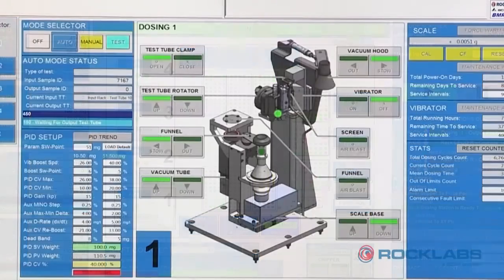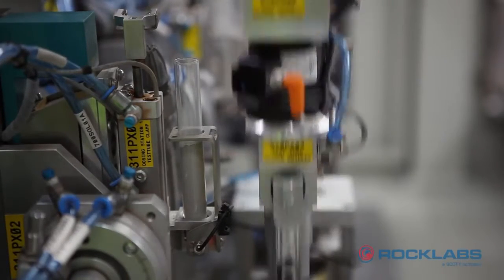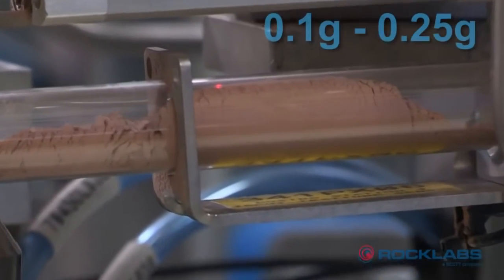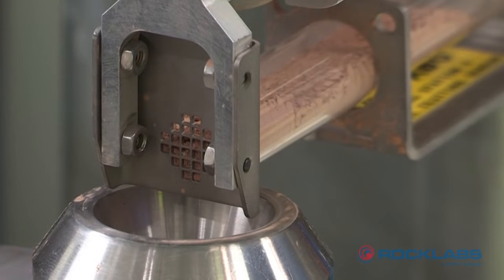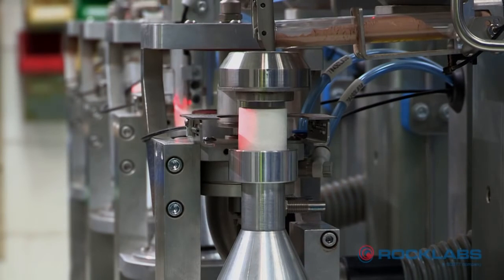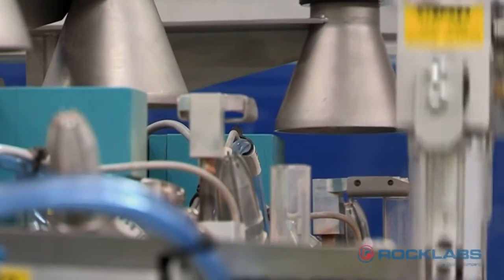There are four standalone dosing units in the AD3000, each equipped with a load cell and a sample dosing mechanism. An output weight is assigned to each sample, usually between 0.1 and 0.25 grams, which is determined from a fully integrated LIMS database in the laboratory. The dosing stations have a self-cleaning cycle utilising air blasts and vacuum.